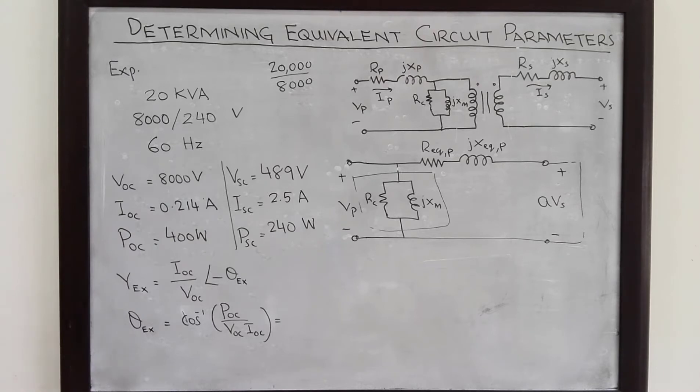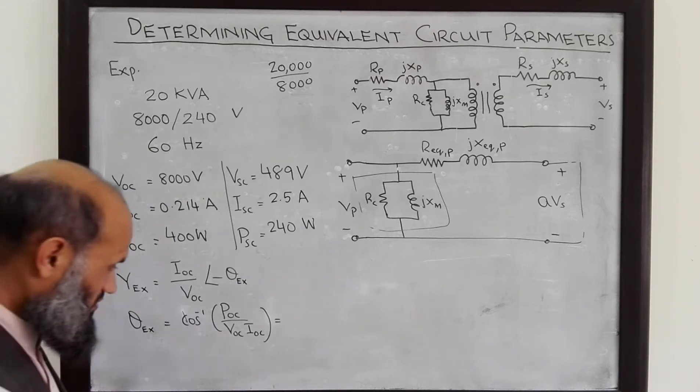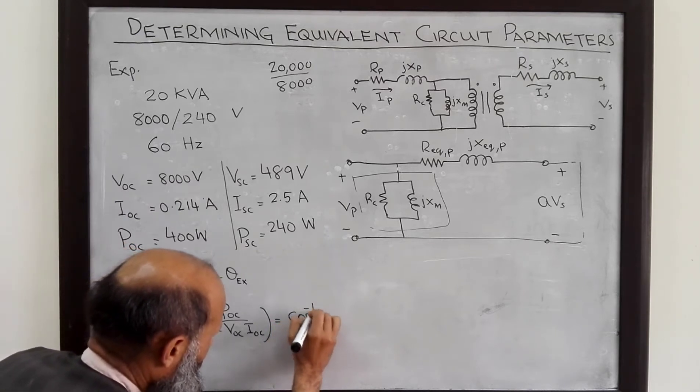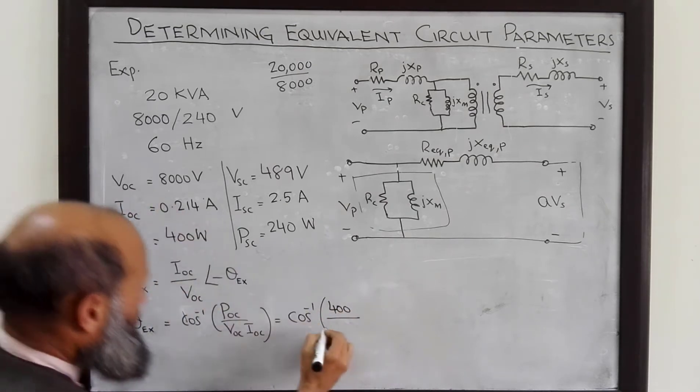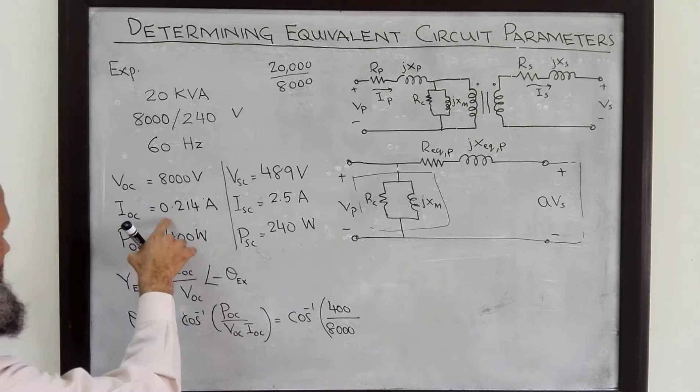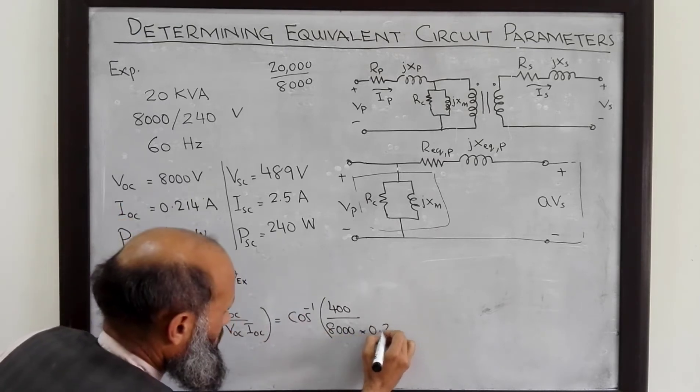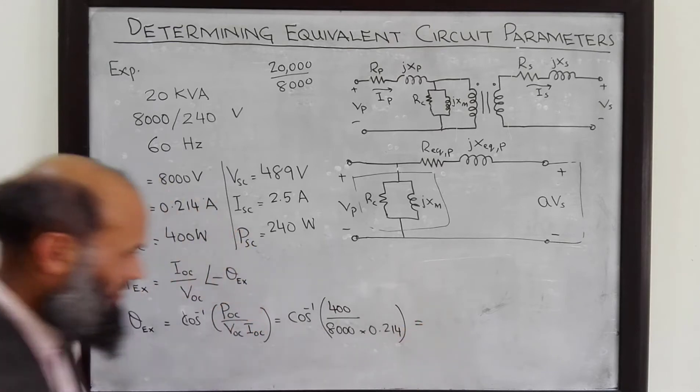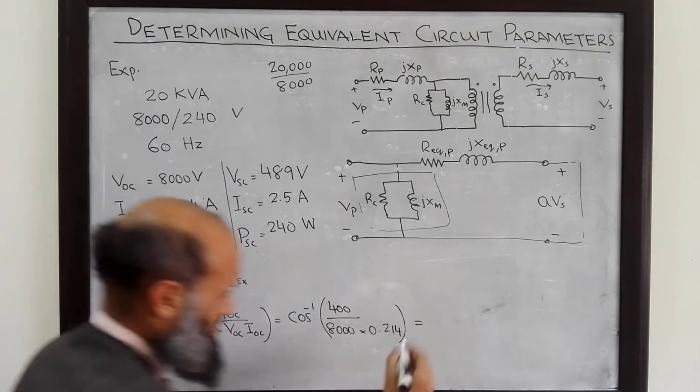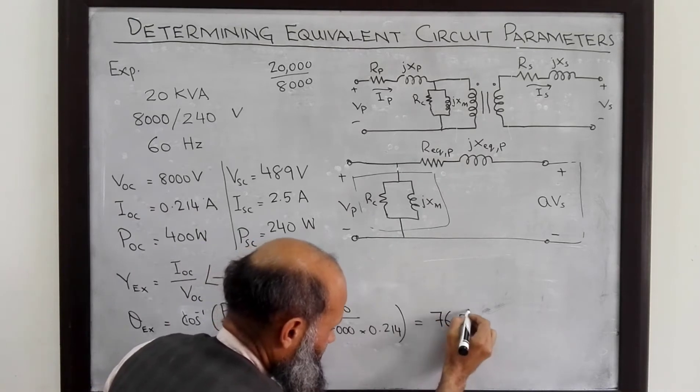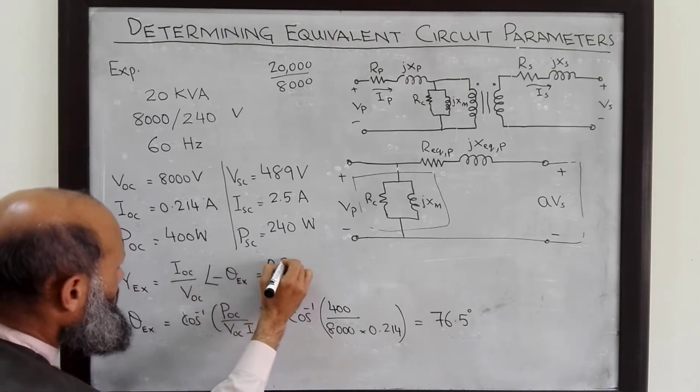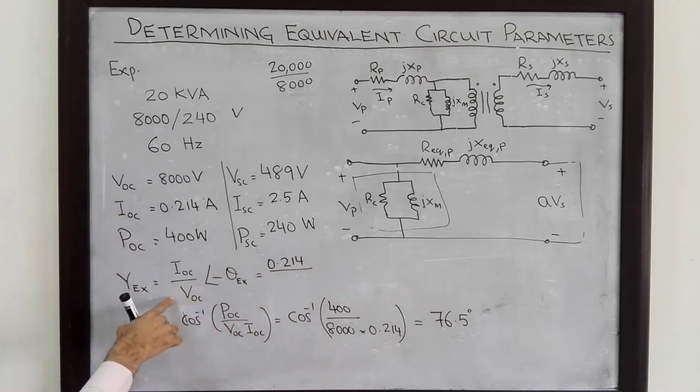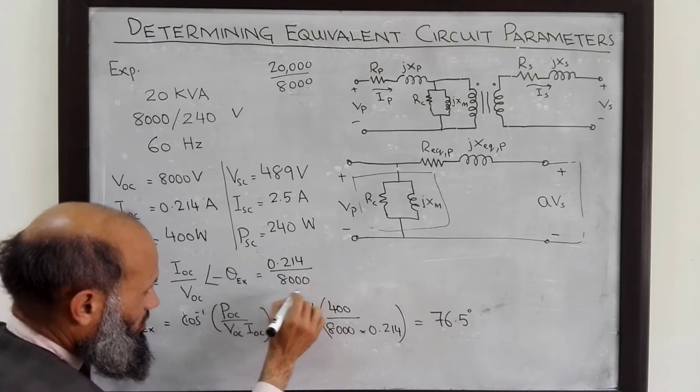So this angle you can determine, it comes out to be equal to 76.5 degrees. Cosine inverse of P open circuit is 400 watts, V open circuit is 8000 volts and I open circuit is 0.214 ampere and this angle comes out to be equal to 76.5 degrees.